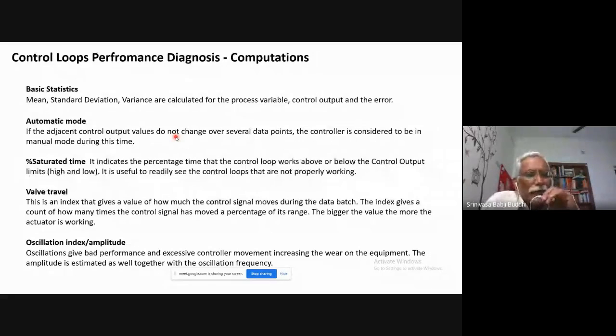Okay. Then percentage of saturation time. This again indicates the percent of time, in the data that has been collected, where the control output signal is staying at the high and low values. This problem we face in several loops. Typically, when you go to the plant and collect the data and do the analysis, you will find many times the control loop's output remaining at the high limit or low limit.